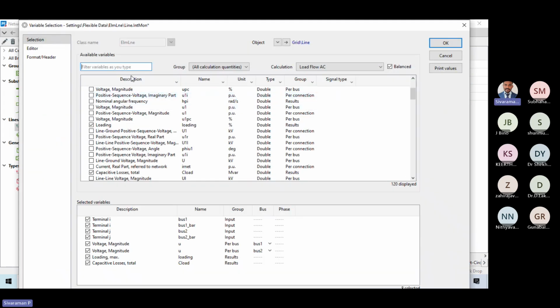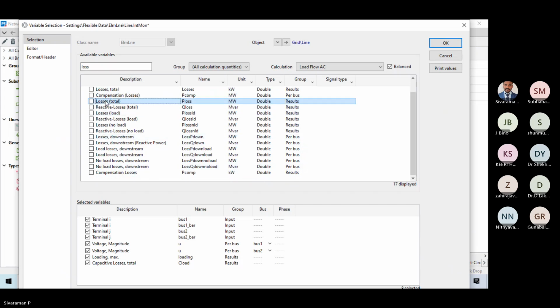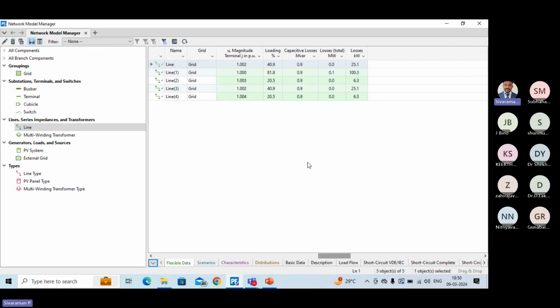We can see how much loss happened in all the cables. For this particular cable, 50.1 kilowatt is the loss. In the next cable, 100.3 kilowatt is the loss, and this cable 6.3 kilowatt, and the next cable 25.1 kilowatt, and this cable 6.3 kilowatt. So if we combine, almost 163 kilowatt is the loss happening in this collector network cable.